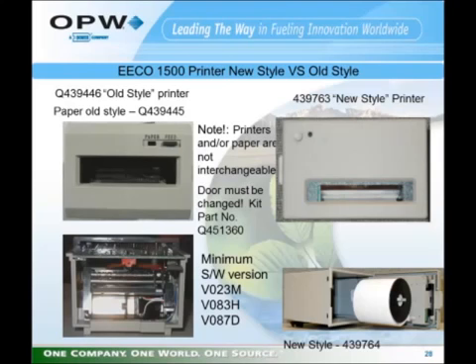Should you have one of those and that printer fails, you need to get the 439763 new style printer. The way that you can tell that it is the new style printer is it has a release button and the door actually swivels open. As the door swivels open, the paper spool comes out where you can change the paper easily. That printer is a different size from the original printer. It will not fit on a EECO 1500 door that supported the old style printer.